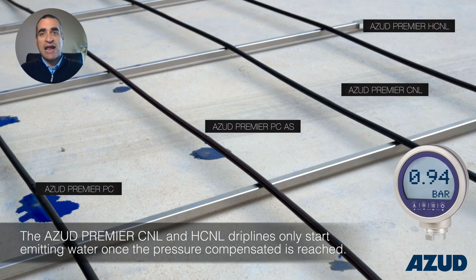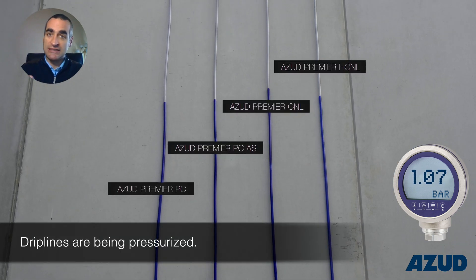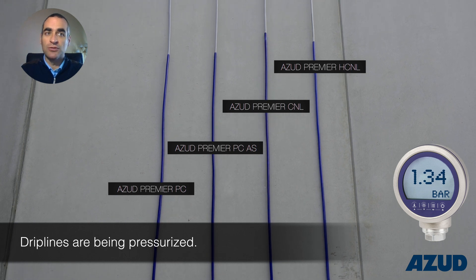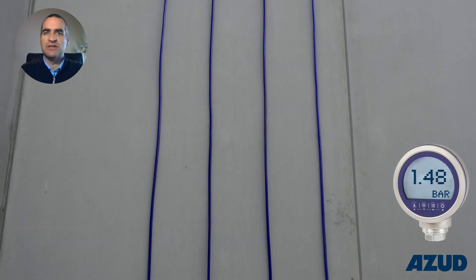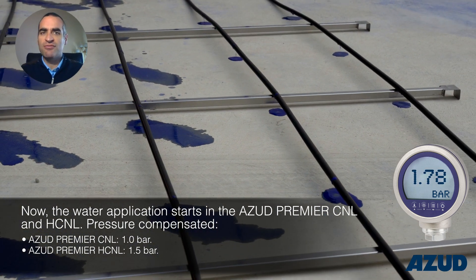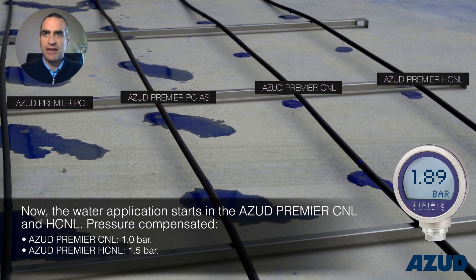On the other hand, in AZUD Premier CNL and HCNL, water starts flowing out when the pressure matches the opening pressure — that is 1 bar for CNL and 1.5 bar for HCNL.